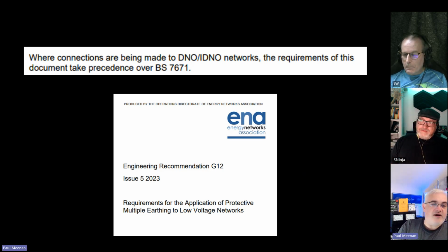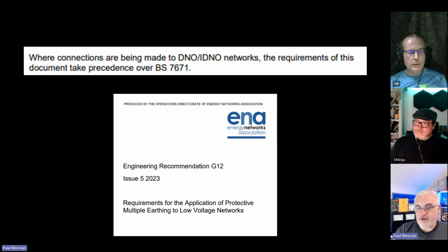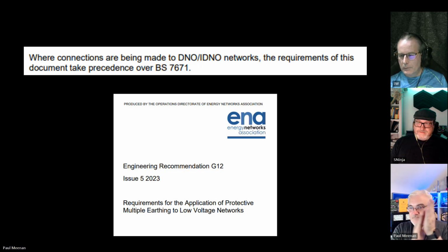So ENA G12, which is the requirements for the application of PME to LV networks. Where connections are being made to DNO networks, the requirements of this document take precedence over 7671. So G12 is a higher standard than BS 7671, although most electricians may not know it exists and may not have a copy. Well done, industry. You're doing a smashing job.